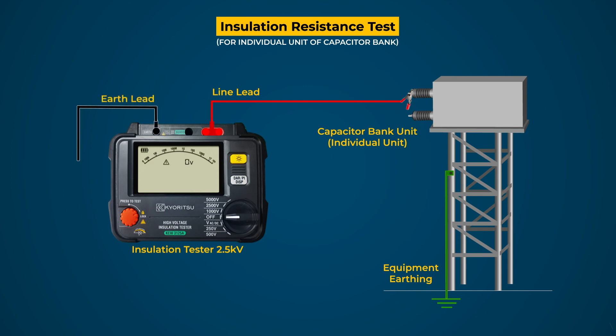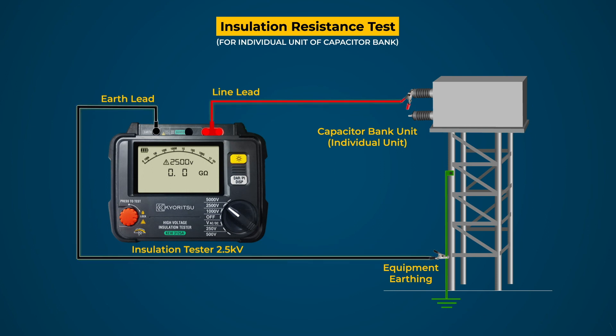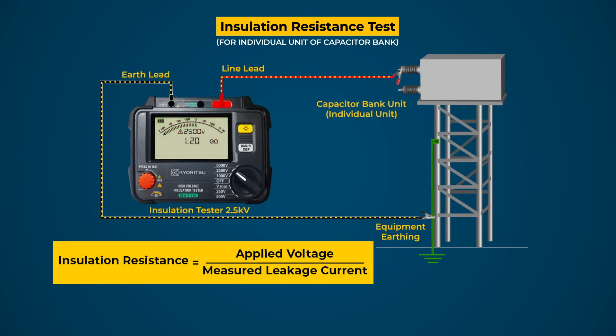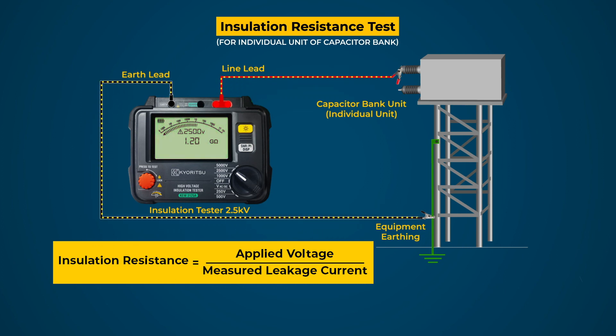For the insulation resistance test of an individual capacitor unit, connect the line terminal of the tester to the terminal of the capacitor unit and the earth terminal of the tester to equipment earthing through leads. Select the test voltage level to 2.5 kV. When the test button is pressed, a DC voltage is applied across the capacitor unit terminal and earthing terminals, causing leakage current to flow. The tester measures this leakage current and calculates the insulation resistance by the ratio of applied voltage to measured leakage current. Record the displayed IR value in megaohms and compare with earlier records or OEM recommendations; if found less, investigate and rectify the issue.